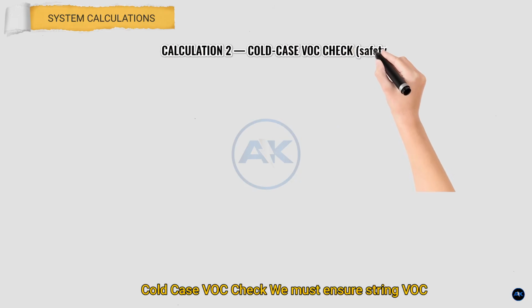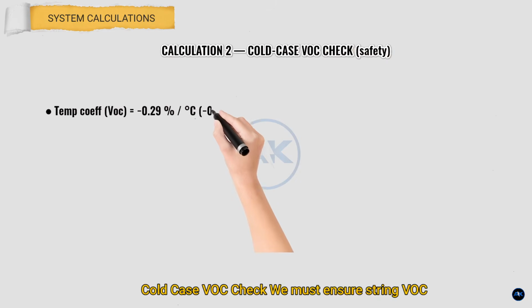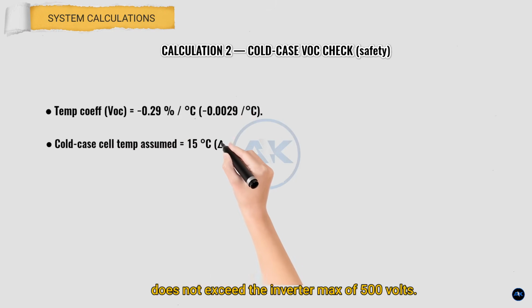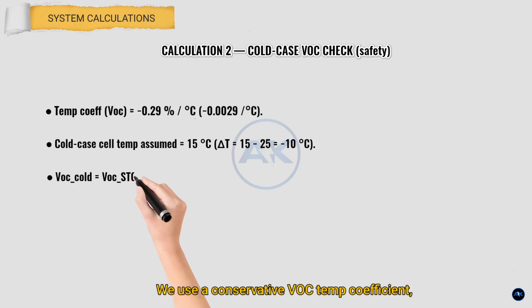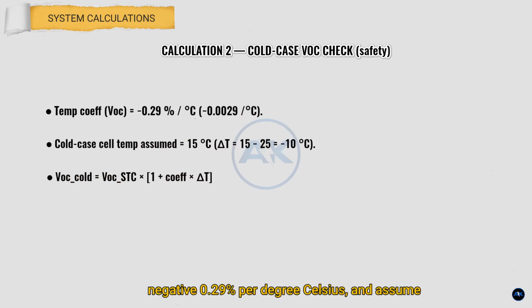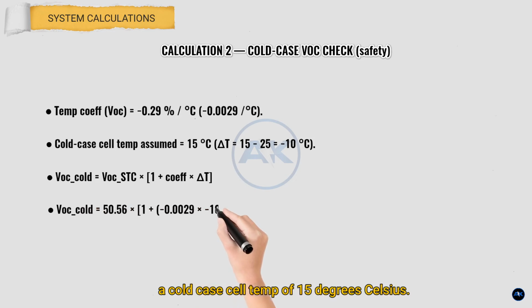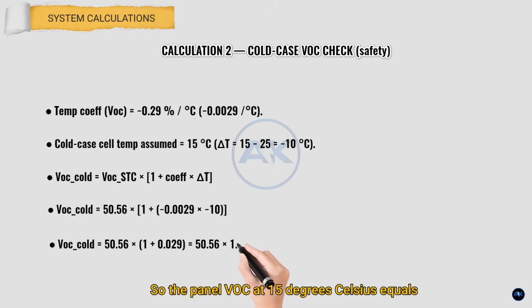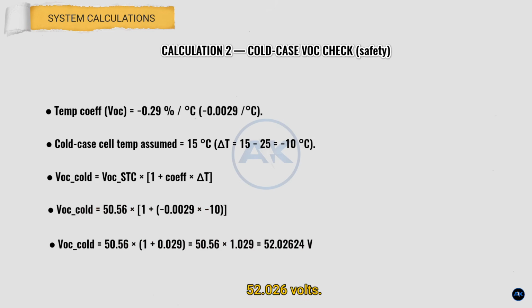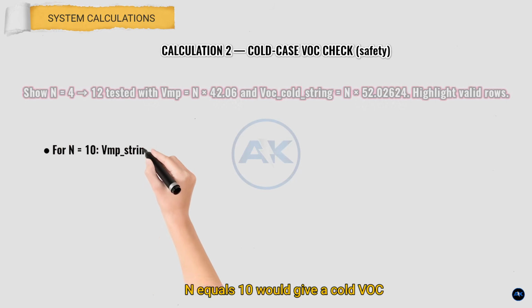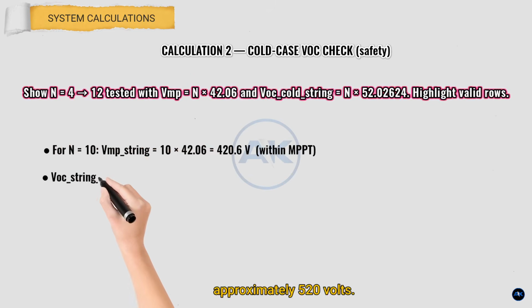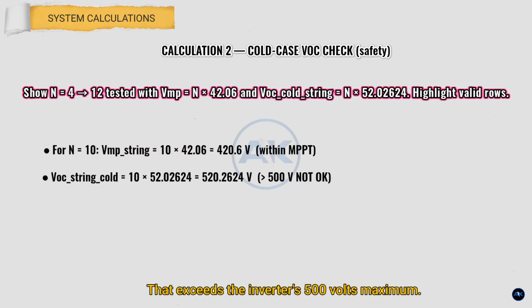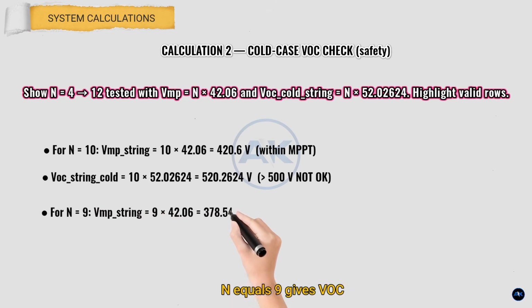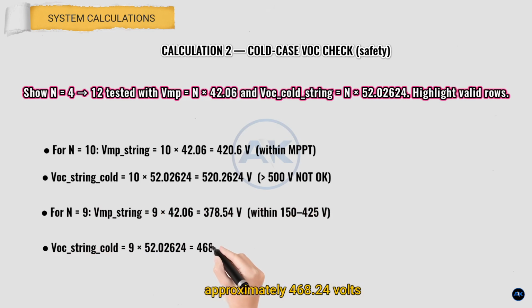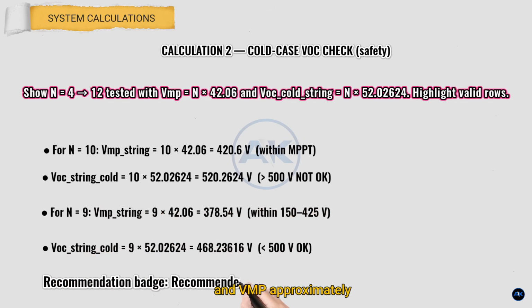Calculation 2. Cold case VOC check. We must ensure string VOC at cold temperatures does not exceed the inverter max of 500 volts. We use a conservative VOC temp coefficient, negative 0.29% per degree Celsius, and assume a cold case cell temp of 15 degrees Celsius. So the panel VOC at 15 degrees Celsius equals 52.026 volts. N equals 10 would give a cold VOC of approximately 520 volts. That exceeds the inverter's 500 volts maximum. N equals 9 gives VOC approximately 468.24 volts and VMP approximately 378.54 volts, which fits comfortably.